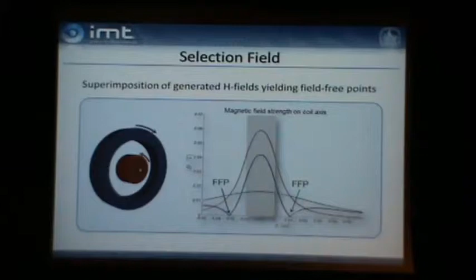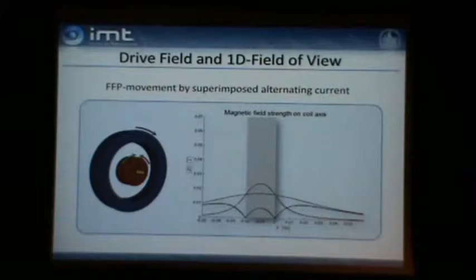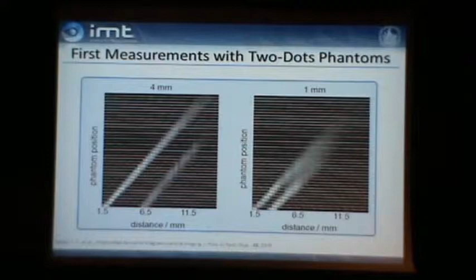Below and before and after this point, we have field strengths. And when we now modulate, for example, the current in the inner coil, then we are able to push and pull the field-free point away and against this device. Okay, so this is one-dimensional excitation, and we did some experiments with two-dot phantoms which we push away from the device, and you see how we can resolve then these two-dot phantoms.